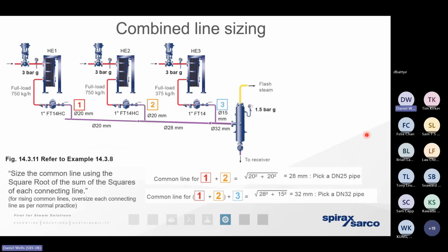So downstream of every steam trap, of course, we need to ensure that every process has its own dedicated steam trap, but there's no reason why those steam traps can't converge in one common infrastructure. They can, providing that we've allowed for the condensate infrastructure to step up in size, not just to accommodate the increased liquid mass of the condensate itself, but also to accommodate any expansion as a result of the condensate that's going to boil off and expand. Again, you can refer to that confusing formula I've put at the bottom of the screen in order to calculate that, or you can refer back to those calculators that we have on our website. The main thing to account for is that we've allowed for not only the mass flow increase, but also the volumetric increase of that flash steam.